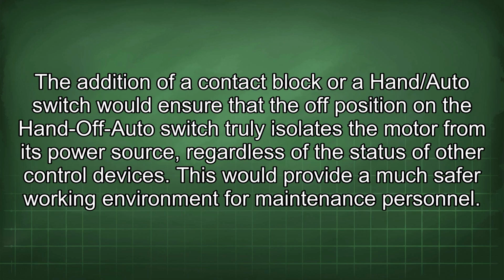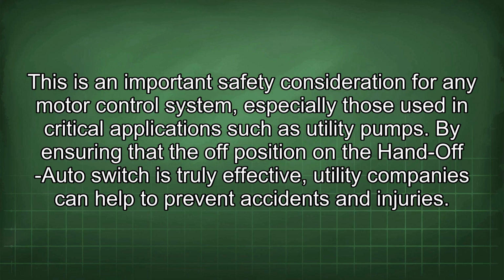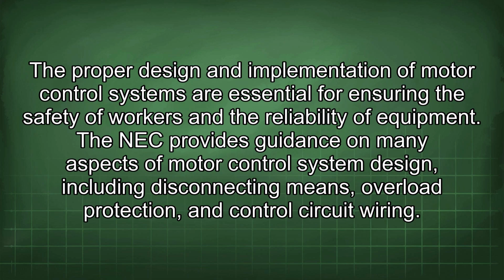The addition of a contact block or a hand/auto switch would ensure that the off position on the hand-off auto switch truly isolates the motor from its power source, regardless of the status of other control devices. This would provide a much safer working environment for maintenance personnel. This is an important safety consideration for any motor control system, especially those used in critical applications such as utility pumps. By ensuring that the off position on the hand-off auto switch is truly effective, utility companies can help to prevent accidents and injuries. The proper design and implementation of motor control systems are essential for ensuring the safety of workers and the reliability of equipment.